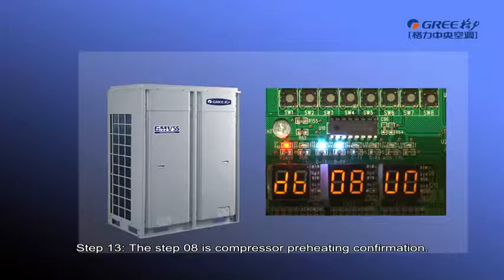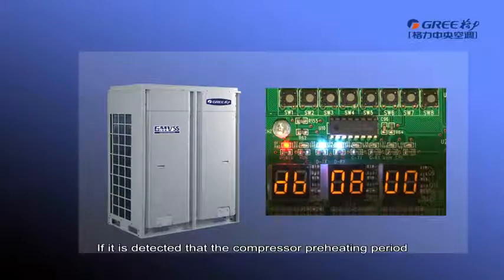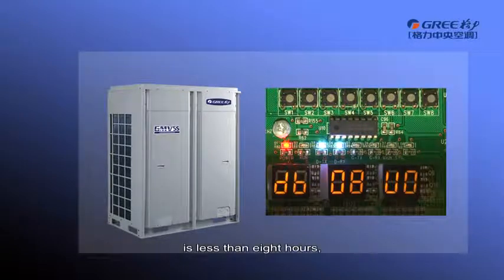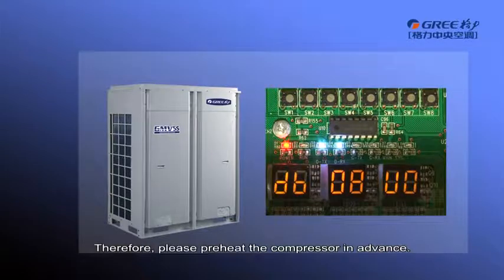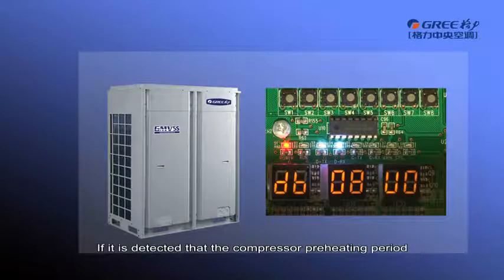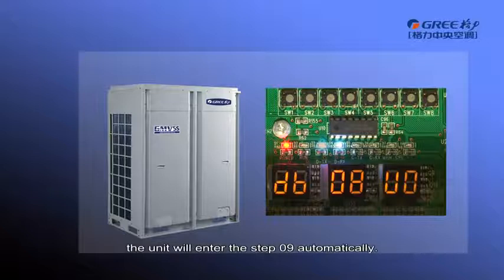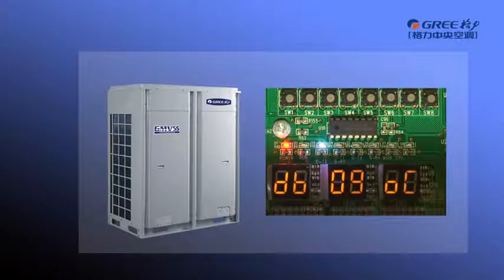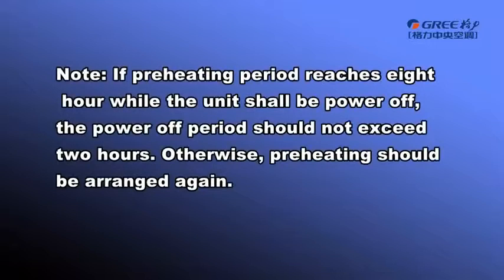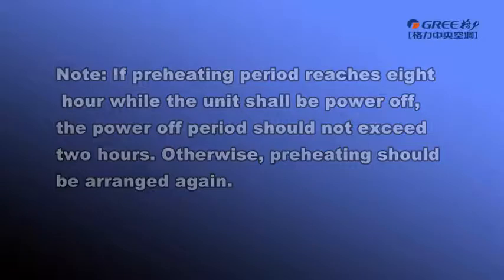Step 13. The Step 08 is compressor preheating confirmation. If it is detected that the compressor preheating period is less than 8 hours, error code U0 will be displayed. Therefore, please preheat the compressor in advance. If it is detected that the compressor preheating period is more than 8 hours, the unit will enter Step 9 automatically. Note, if preheating period reaches 8 hours while the unit shall be power off, the power off period shall not exceed 2 hours. Otherwise, preheating shall be arranged again.